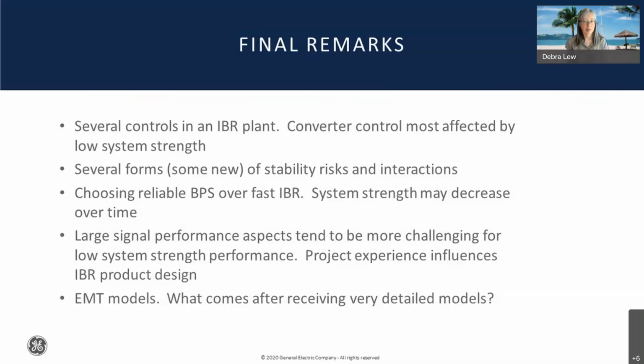Not necessarily - actually the opposite can be true. If you do momentary cessation, you'll be interrupting power for some time after the fault. That's not the only way of reducing power injection. What I was referring to before was a control where the inverter-based resource keeps controllability during and after the fault, but you recover power after the fault not too fast, in low system strength conditions.